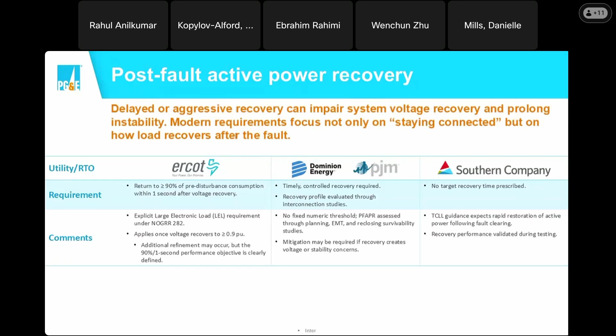One common theme with the post-fault active power recovery is the return to 90% of pre-disturbance consumption within about 1 second after the voltage recovers to pre-fault values. Maybe not even to pre-fault values, but at least to like 0.9 per unit. That's a very common theme that we see in terms of a post-fault active power voltage recovery requirement.